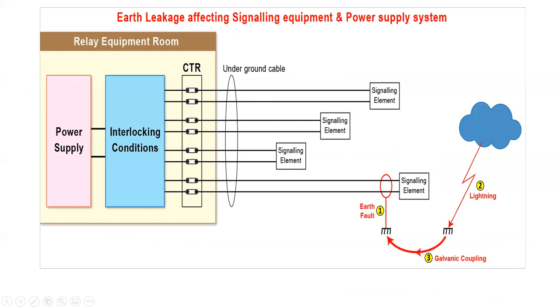Now, let us see how earth leakage or low insulation affects the electronics, that is, the axle counter. Let us consider this case. This is the signaling element, whatever it may be, it can be an SSDAC. Now there is an earth fault already available. The earth fault is not one that causes a failure of the equipment, maybe 20 kilo ohms. Now, when the lightning occurs, it enters into the earth. While entering into the earth, if it lands nearer to this earth fault, a galvanic coupling takes place between the two, and the surge enters into the signaling element and damages it. That is why we have to see that the proper insulation resistance with respect to earth and with respect to the other conductors is maintained.